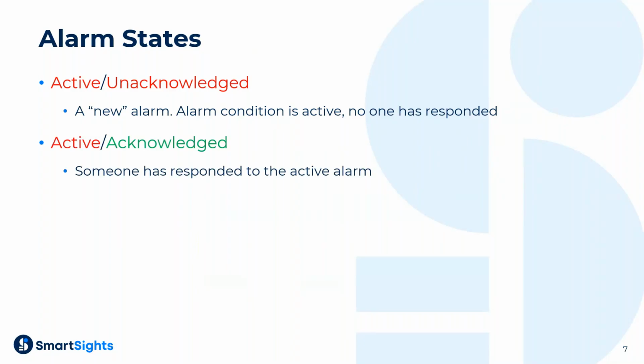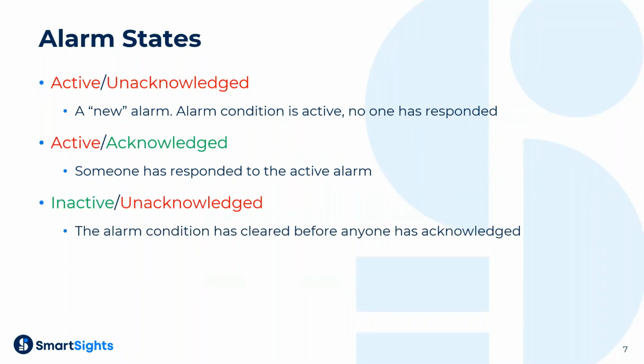Active acknowledged means someone has responded to the active alarm. That way other people in the plant, other users of the HMI SCADA system, understand that they don't have to respond to that alarm because someone else has.